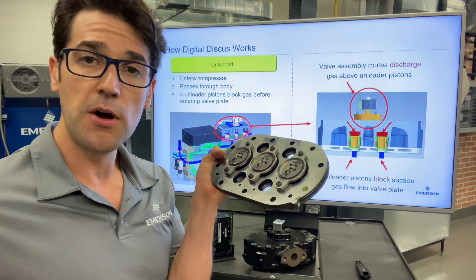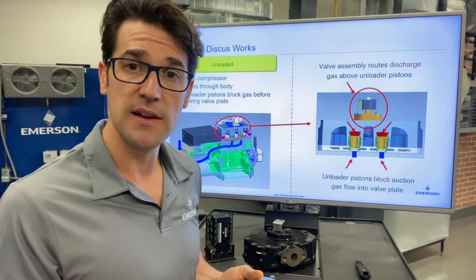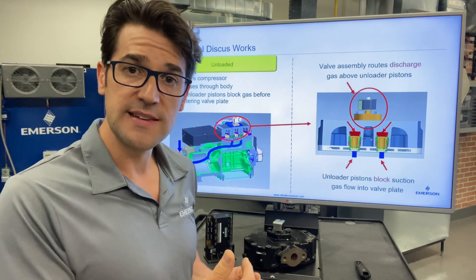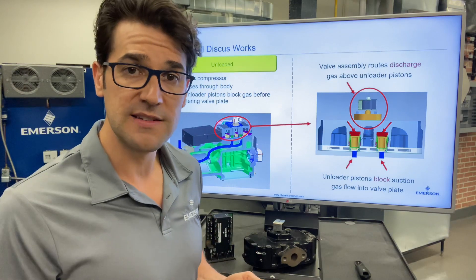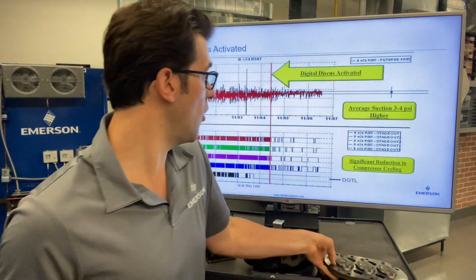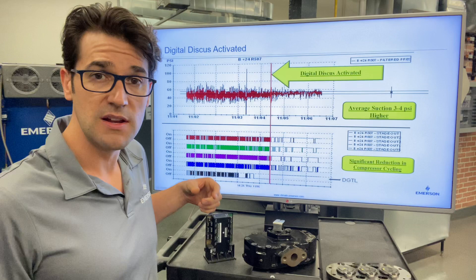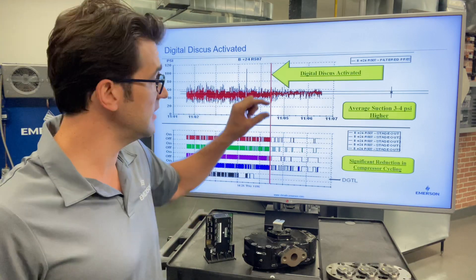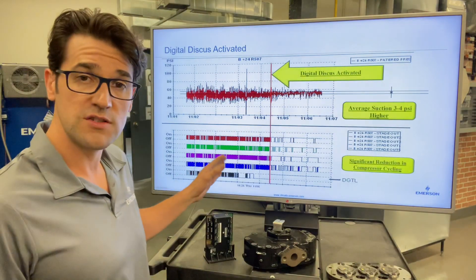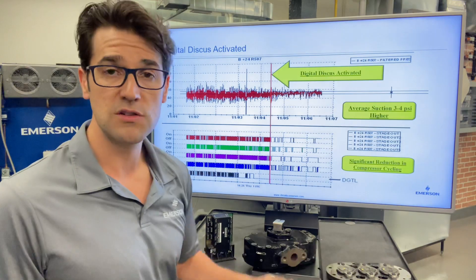And that's done on pulse width modulation. This is a digital compressor, so it can go from 10% to 100%. So if it's loaded for 10 seconds and then unloaded for 10 seconds, that's 50% capacity. You can take your suction on a multiple compressor application where it's got a massive range and turn it down into a few PSI range. And then you take hundreds and hundreds of cycles a day on the multiple compressor application down to very minimal — it could be less than 20.